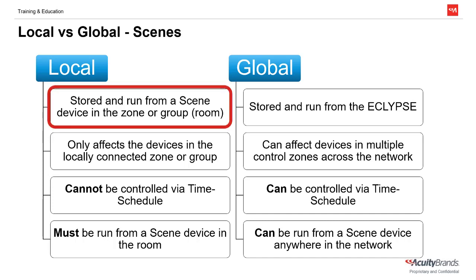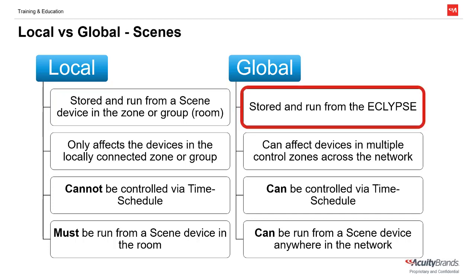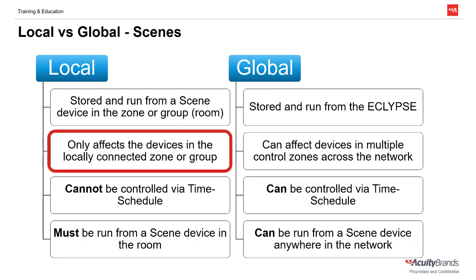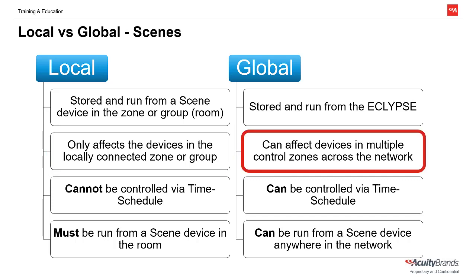Local scenes are stored on and run from a device in the lighting control zone or room. This device must be a scene controller like an nPod M1, 2, or 4S, a Neo 1S, or an nPod Touch. Global scenes are stored on and run from the nLight Eclipse or older style gateway. Local scenes can only affect devices in the immediate group or wired zone, typically the room. Global scenes can affect devices across the entire network, regardless of their location, as long as they're within the same nLight network.